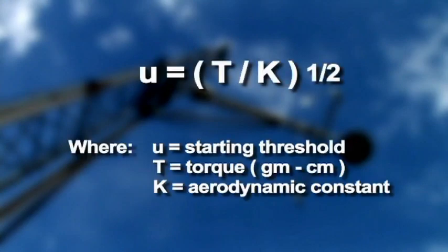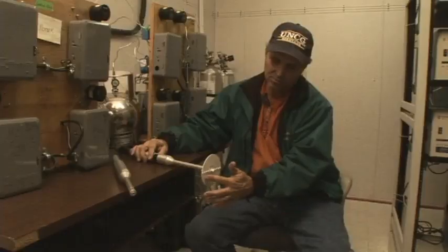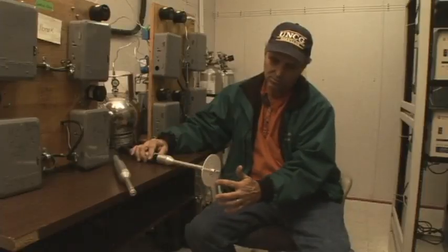The EPA QA Handbook on Meteorological Measurements, Section 2.5.1.1, has the equation converting the torque to meters per second. Reference your manufacturer's manual for the optimal starting threshold for your sensor. If the starting threshold is above the recommended value, then the bearings must be replaced. Retest the torque after you have replaced the bearings. This now concludes the wind direction calibration.